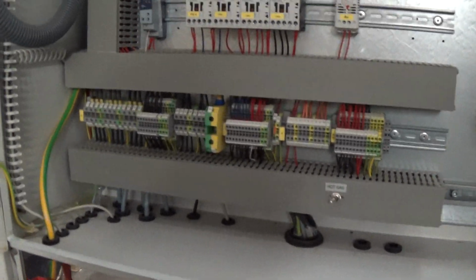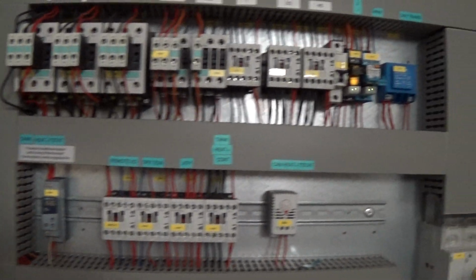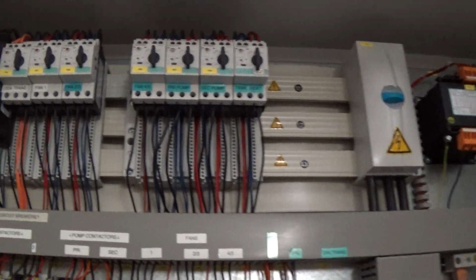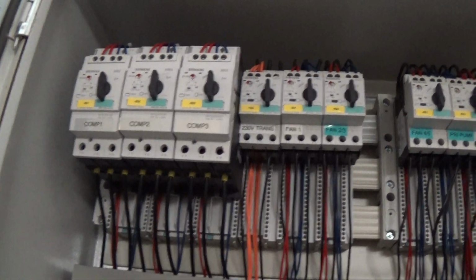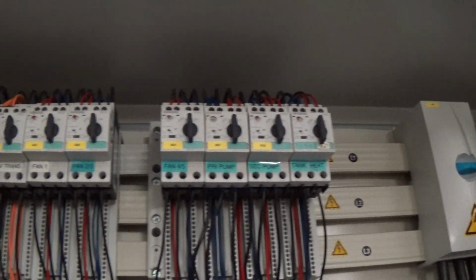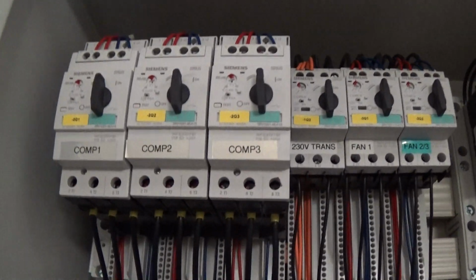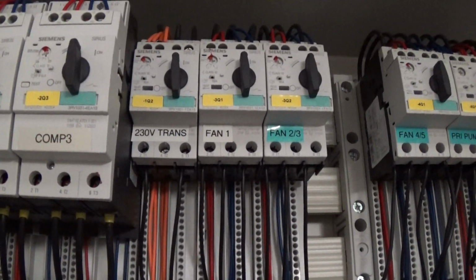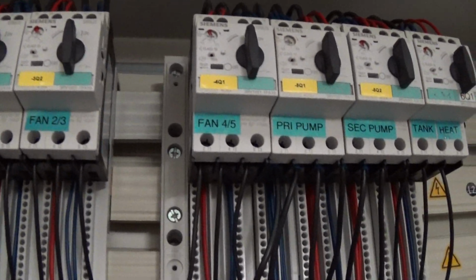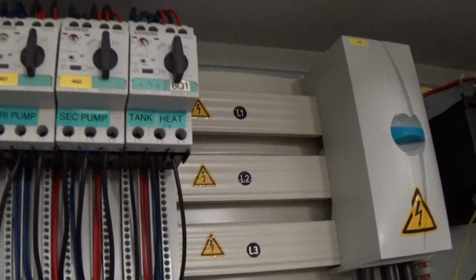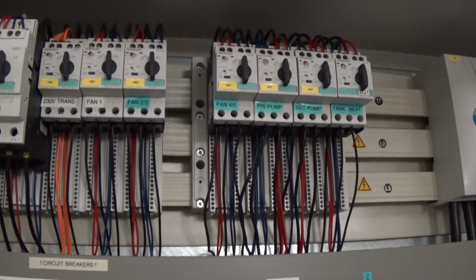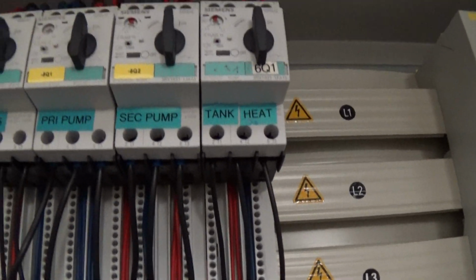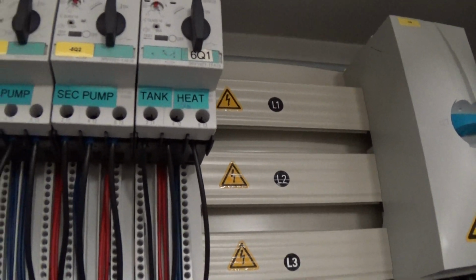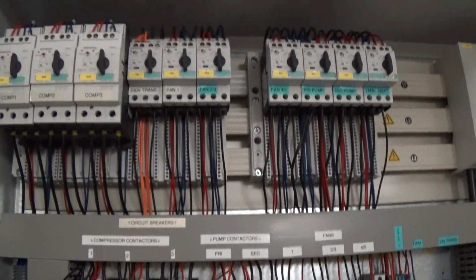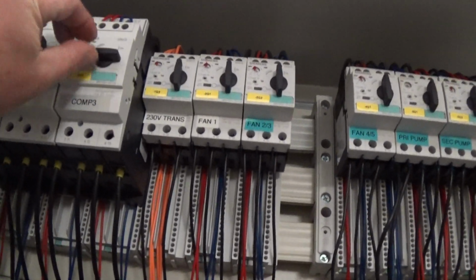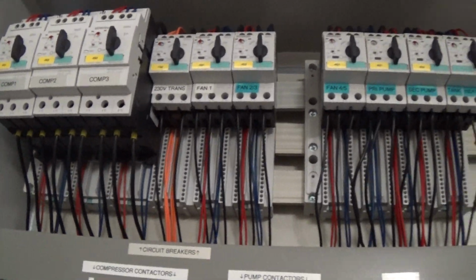Here in our control cabinet, I advised our technician to label all the key components in here. Up here are your overloads. All of them you'll see are in the vertical position. If one of these overloads trip, in fact you can see compressor 1, compressor 2, compressor 3, or fan 1, and then fan 2 of 3, fan 4 of 5, etc. There's five fans up above. Then you can see primary pump, secondary pump, tank heater. There's a heater for the tank. If those were to trip, the switch would go to that position there, and that's how you reset it.